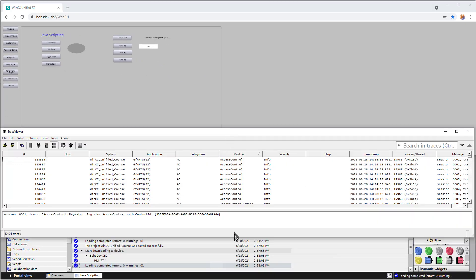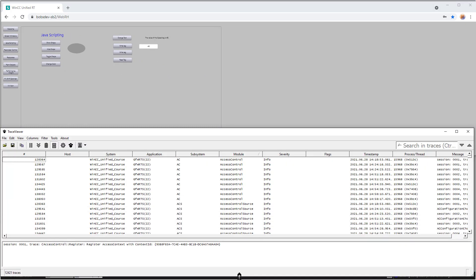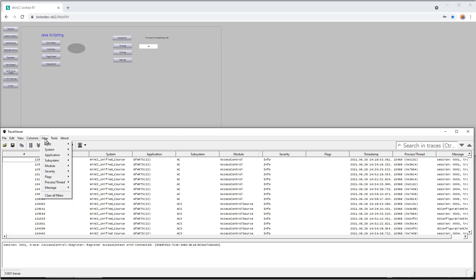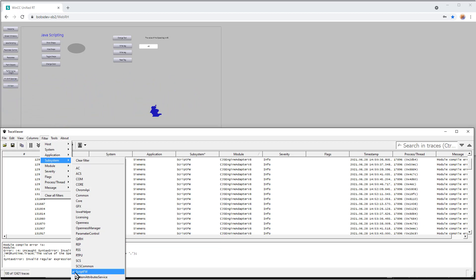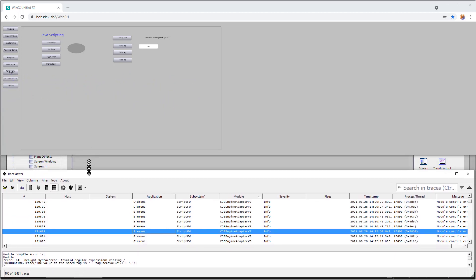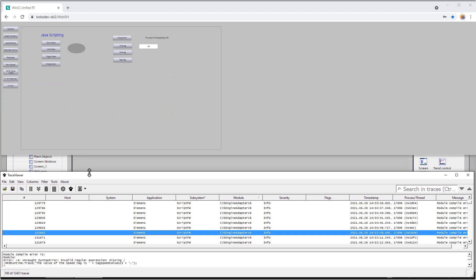So I'm going to make my runtime window small, so that we can have both the trace viewer and runtime up. And you can see there's a lot of entries already here. So the trace viewer shows traces from many different TIA portal subsystems and Windows services. So we're going to use the filter function to filter only for runtime scripting events, script FW. So you can see there's a checkbox there. I'll make this a little smaller now.